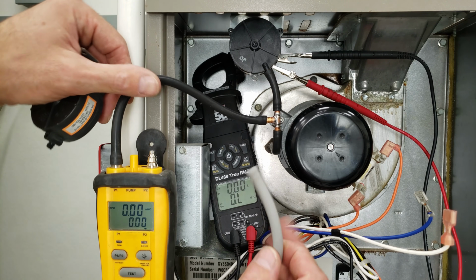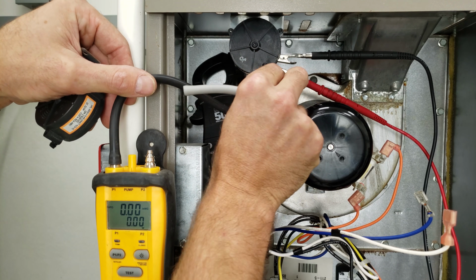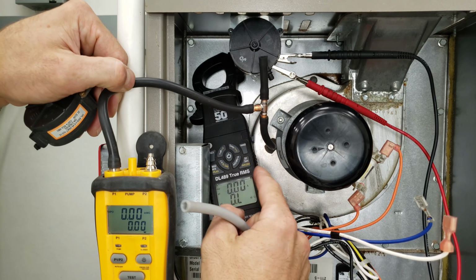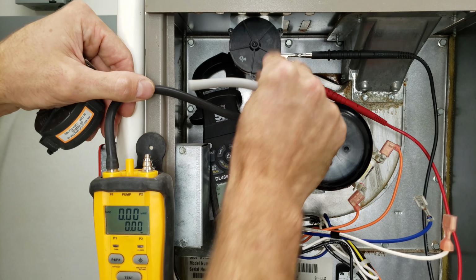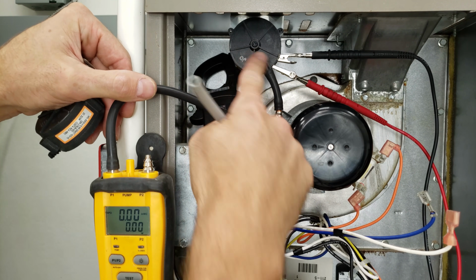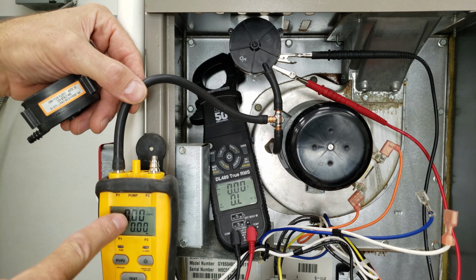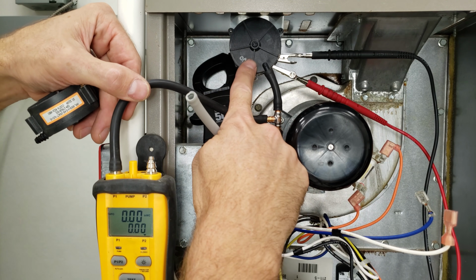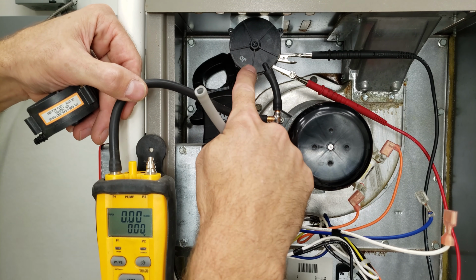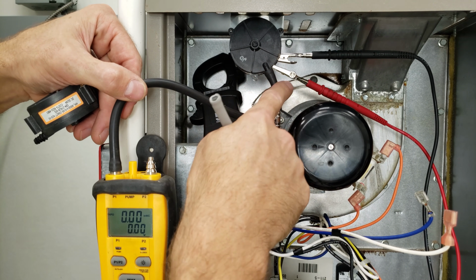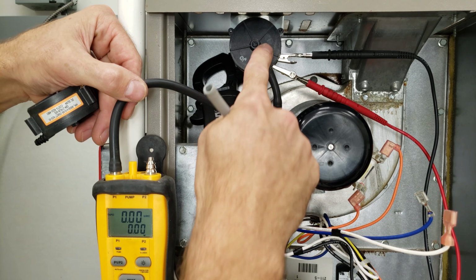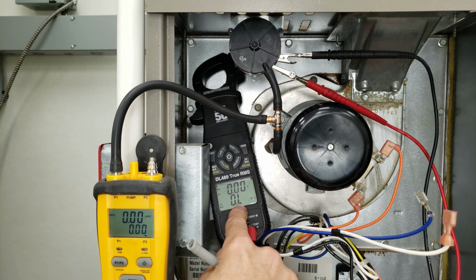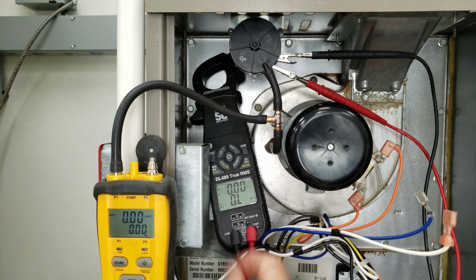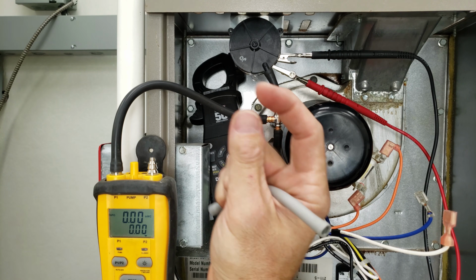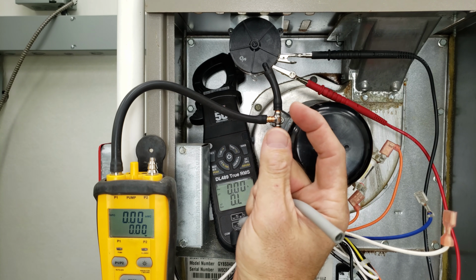So we're at our gas furnace. Here's our single port pressure switch, and we just have this little T in place. We're teeing in between the inducer motor housing and the pressure switch to measure our inches of water column. So we're measuring the pressure reduction on this side of the pressure switch. Here I have 2 probes, and we're measuring the electrical resistance across the switch. OL means open line, over limit. Basically, it just means that there's an air gap and the switch is open presently.